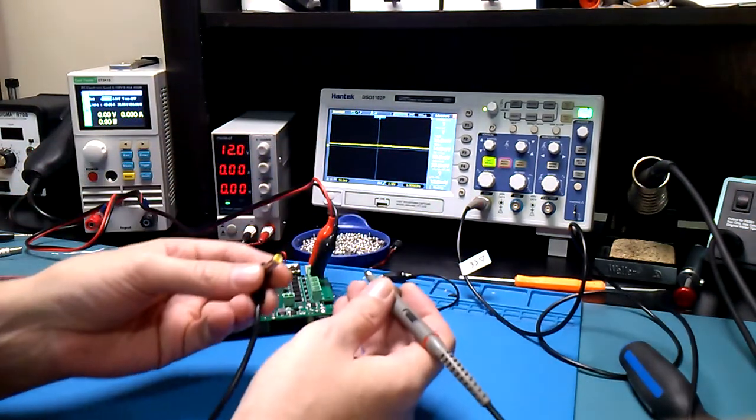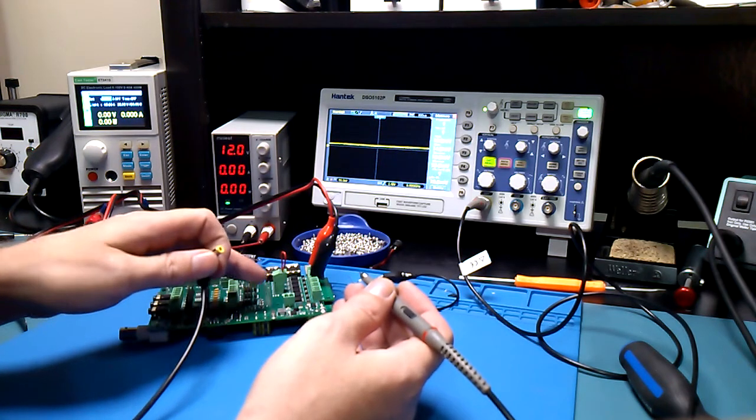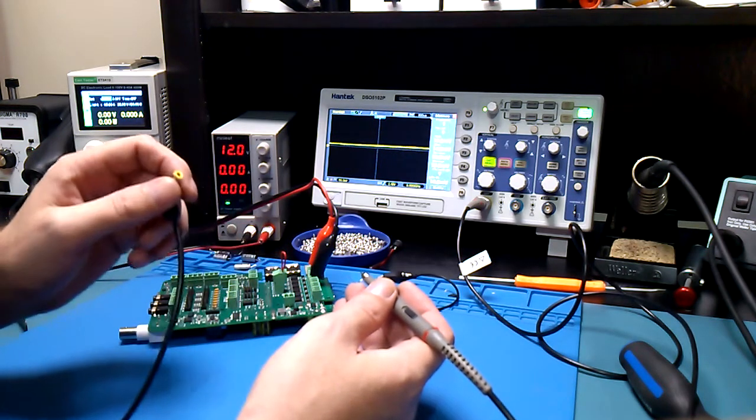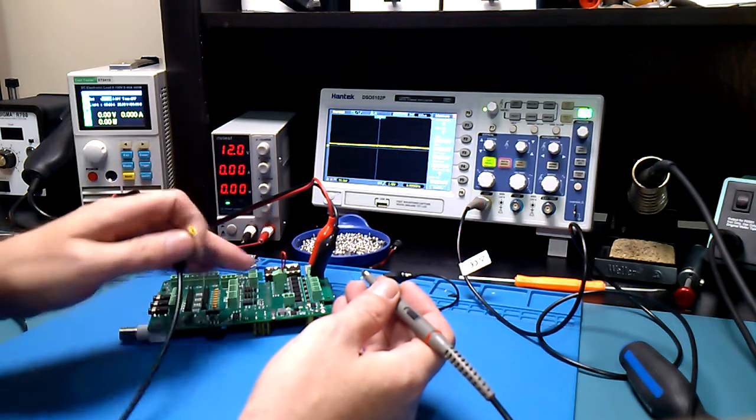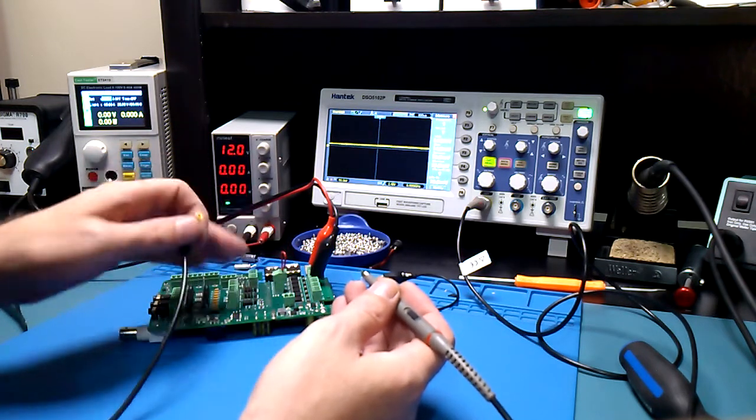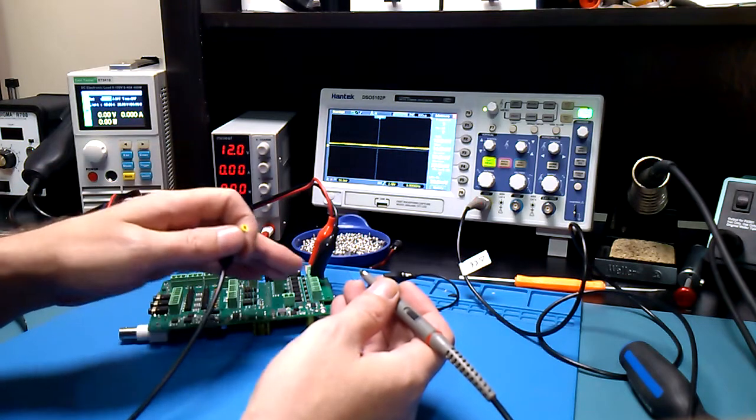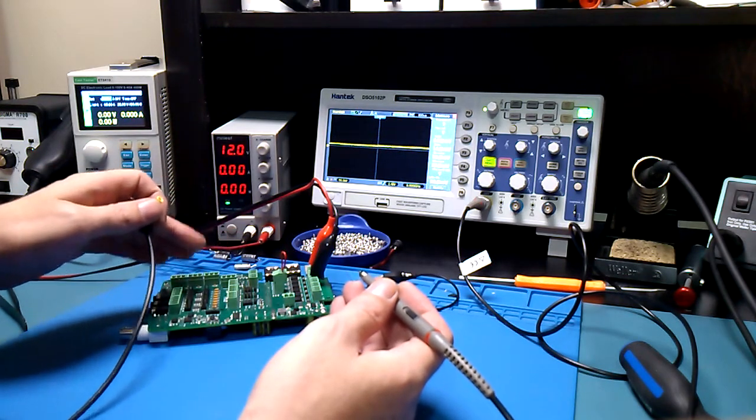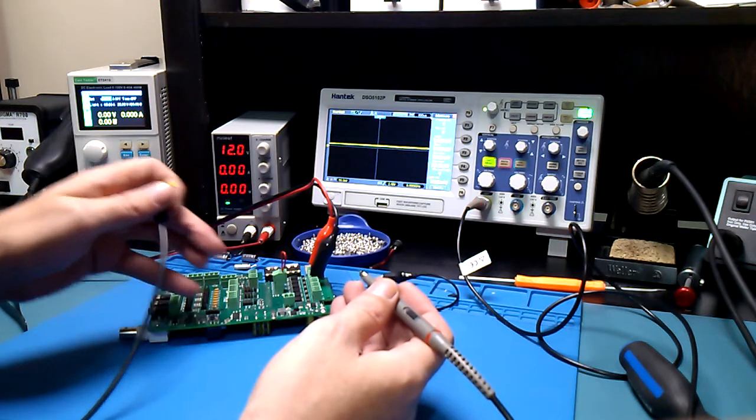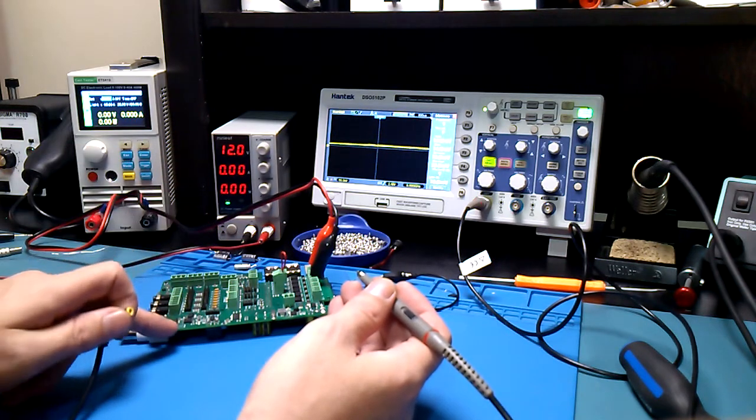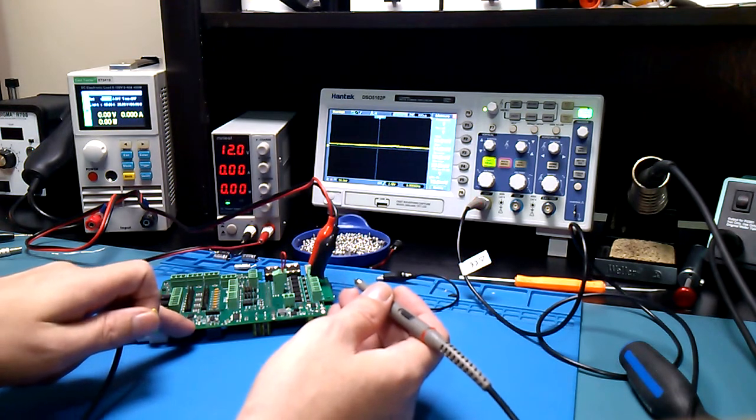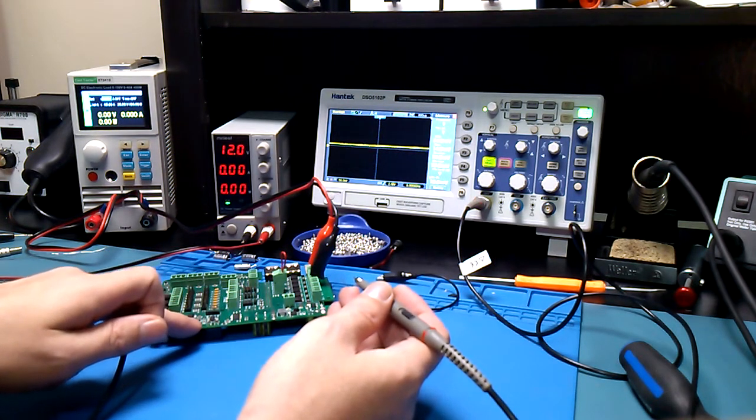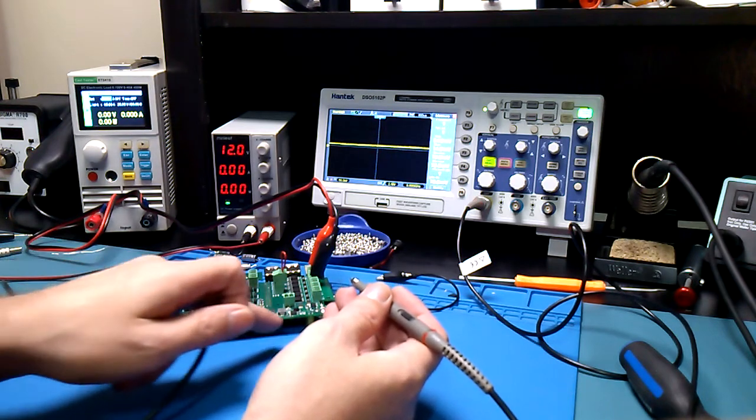We'll start with our DC ripple. What DC ripple is - all power supplies have a rating for DC ripple, and it just says how clean the power supply is. DC ripple can cause various effects. It can be hard on components. Sensitive circuits are affected by it, like our pH, for example. pH is based on voltage, so if our voltage is spiking up and down, our pH will change accordingly.